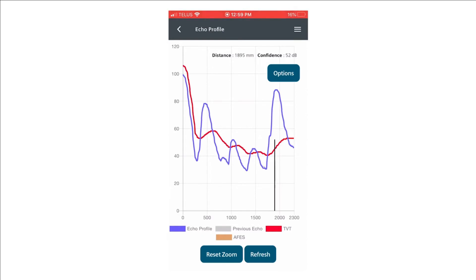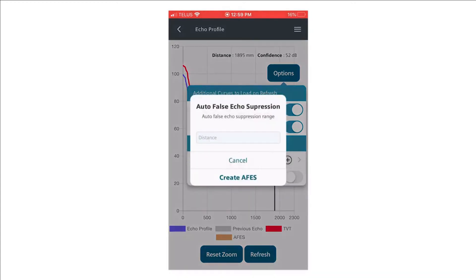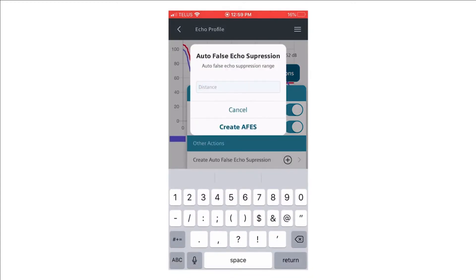To use the auto-false echo suppression feature, we click Options, allow the false echo suppression curve to be displayed—that's the second button—we want to create a new one. We will enter a distance of about 1,900 millimeters. This is the distance to the known target or level.